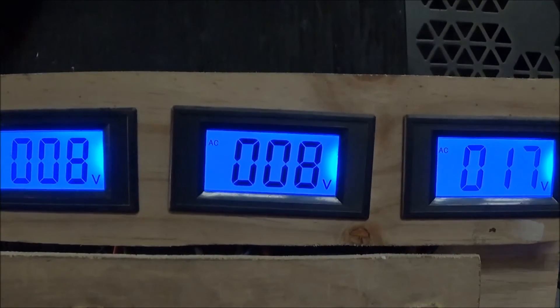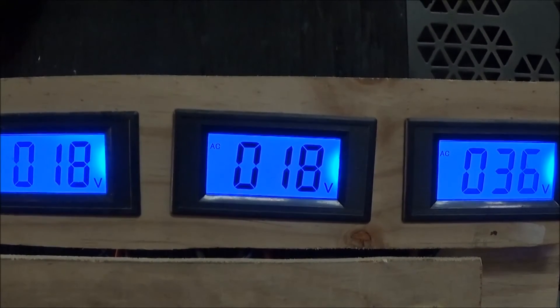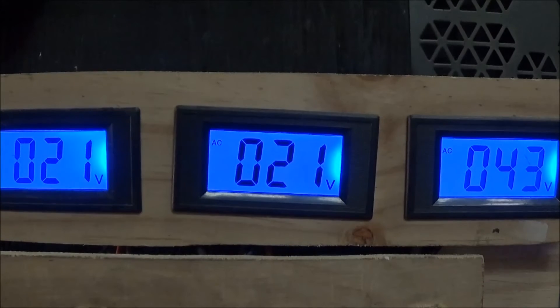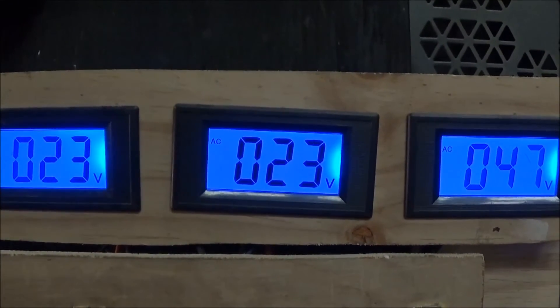This time, as you see the voltage numbers going up, obviously one of them is twice the other two. One of our generator winds is dead here. There's a major phase imbalance. This stator is definitely bad.